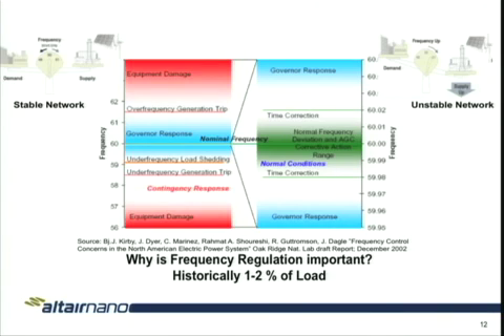Well, you should, because it's pretty important. It's happening all the time, and there's actually a lot of money being spent on it. And why is it so important? We have two charts here, stable network going from 56 to 63, although hopefully you'll never get there. But equipment damage here, typically you're at this point, you're going through over voltage events. At that point, maybe you did have some substation shut down or trip offline, or maybe a large portion of the grid, a transmission line like can happen, and suddenly you have too much generation and your voltage builds up and you start blowing circuits, and hopefully before then you'll be tripping your protective relays.